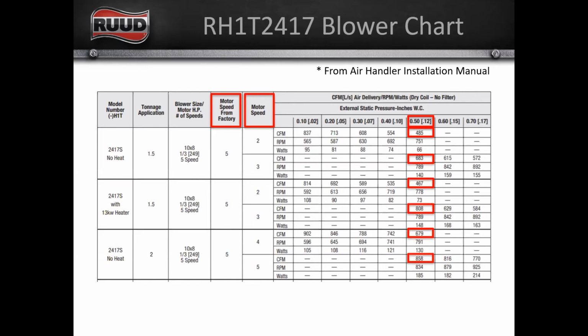Now we don't know what your application is. This would be a starting point, right? And so at 0.5, this same air handler could be moving anywhere from 485 cubic feet per minute to 858 cubic feet per minute. That's a huge difference, right? And so we have to pull the panel off to see what blower tap we are using before we can really determine how much air we're moving. And I will tell you from my experience that most systems out there today are still wired on tap 5. They always have been. Nobody ever changed it. Nobody ever looked at it.